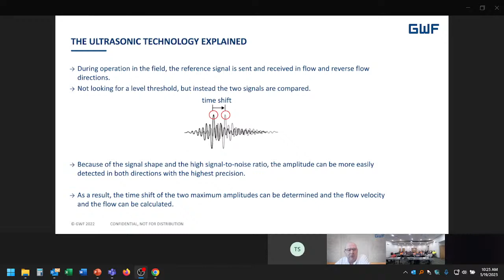By doing this, we're able to avoid more noise, because we can detect the amplitude more easily in both directions. And because of this time shift, we can look at a much higher resolution as to the flow velocity and how that flow can be calculated. This will effectively remove the need for upstream and downstream conditions. We jumped over a slide, unfortunately. Let me see if I can bring this up here. So what this allows for is removing the need for upstream and downstream conditions, especially with more paths.